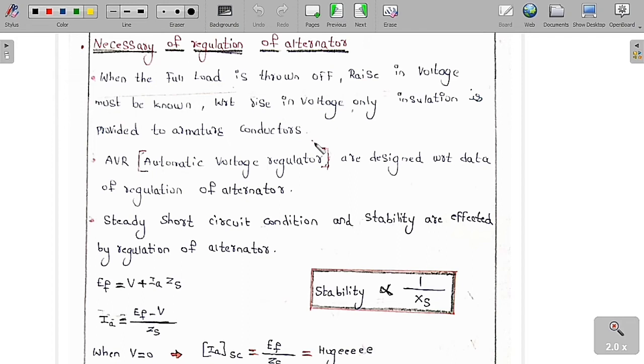So whenever the full load is thrown off, there is a rise in voltage. You must know how much the voltage rises. Based on that, you can provide the insulation to the armature conductors. At full load, the voltage across the load is minimum. At no load, the voltage across the load is maximum. So whenever the full load is thrown off, the rise in voltage must be known, because insulation is provided to the armature conductors with respect to it.